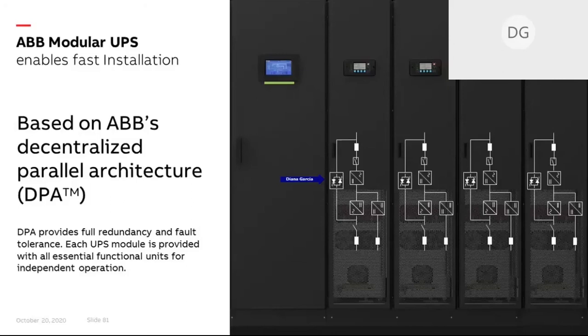Further, the DPA architecture allows online swap capability for power modules, providing continuous business uptime. Online swap means a module can be removed and inserted without the need to power down or transfer to raw main supply. This aspect improves serviceability and availability. As IT demand can increase very fast — especially in co-locations — the UPS power requirement must respond to this need. The modular nature of DPA makes it easy to add modules or increase power capabilities without over-specifying the initial configuration.